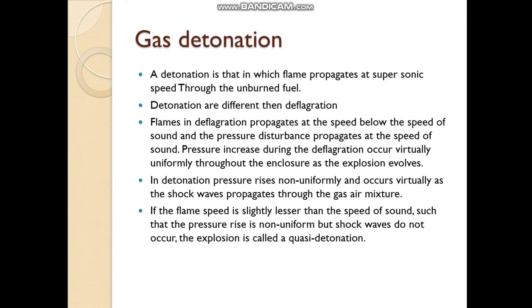Gas detonation: in gas detonation, the flame propagates through the unburnt fuel at supersonic speed. In deflagration, the flame propagates below the speed of sound, while the pressure disturbance propagates at the speed of sound. The pressure increase during deflagration is virtually uniform throughout the enclosure as the explosion evolves. In detonation, however, the pressure is non-uniform and shock waves propagate through the gas-air mixture.